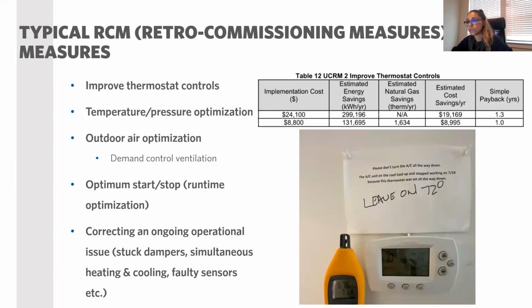And the others obviously depend on the HVAC type. With more complicated systems, we get into more temperature, pressure optimizations or outdoor air optimizations. Outdoor air is sometimes tricky because sometimes we see the outdoor air dampers are closed in the buildings, and that is not bringing in the minimum outdoor air that's required, which is a code violation. But on the other hand, opening the damper will cause more energy use, so it actually turns into a penalty, but we still want to correct the operation, obviously. But if everything is working fine, then we implement demand control ventilation for the areas that are applicable by code to save energy.